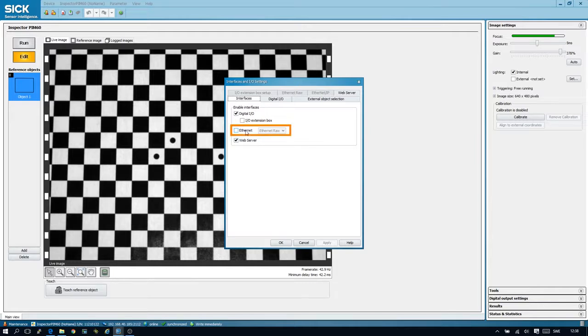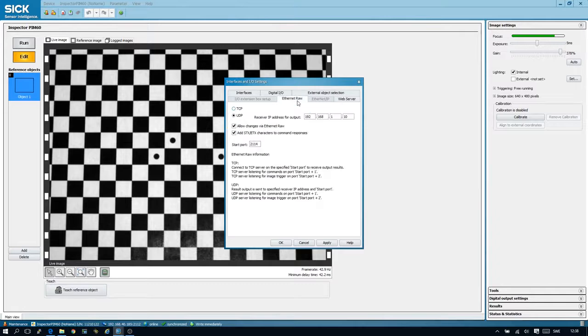First, we need to set Ethernet and Ethernet raw. We need to make sure the web server is enabled, and in the web server tab make sure it runs on port 80 and that allow changes via web server is enabled. We also need to change some things in the Ethernet raw tab, where we set it to TCP communication. Make sure allow changes via Ethernet raw is set, that STX and ETX are enabled, and that the start port is 2114.